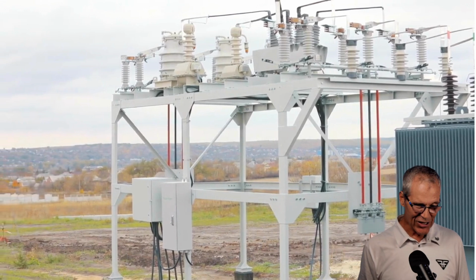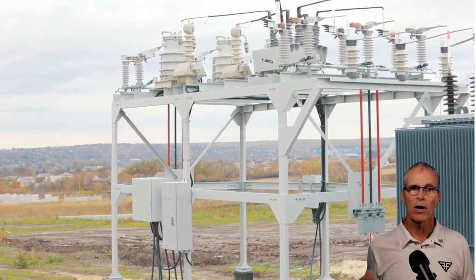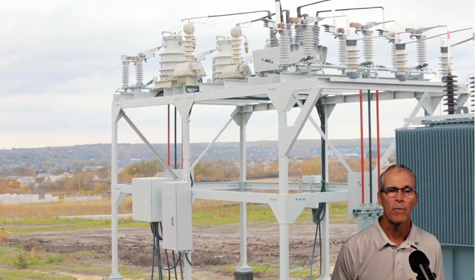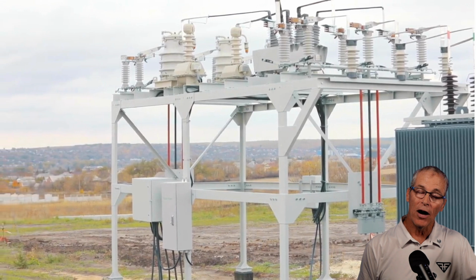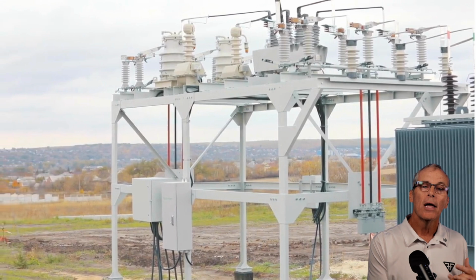I went out to a facility and saw fans just clipped out of their inverter cases, thrown on the ground. They were laying around, and I saw the dirty air filters, and I realized, okay, this is easy. You can't wait for the manufacturer's recommended time period of 6 months. You need to be coming out here as soon as the compartment overheats, but you need to come out here when that fan fails, or if before that, every month or two.